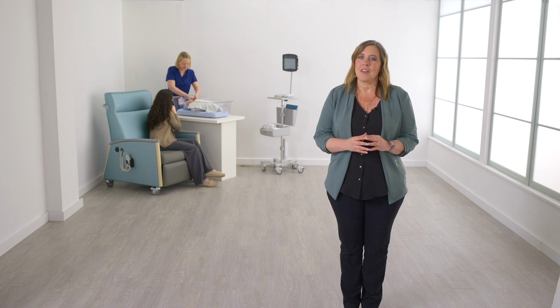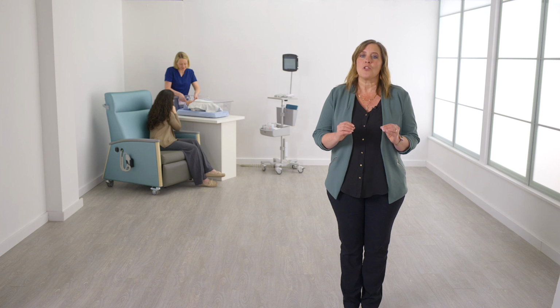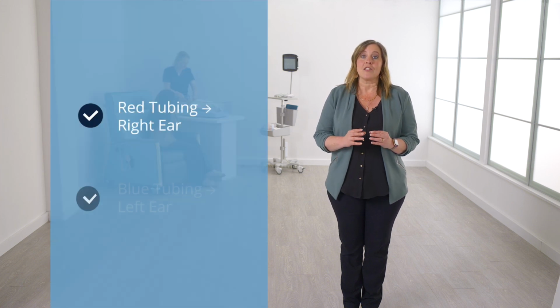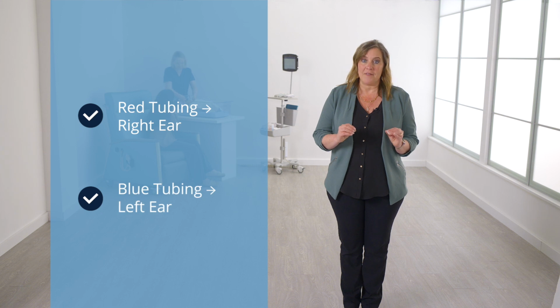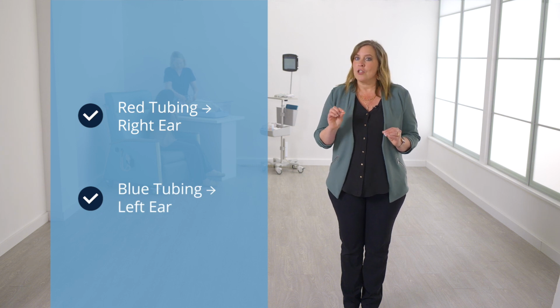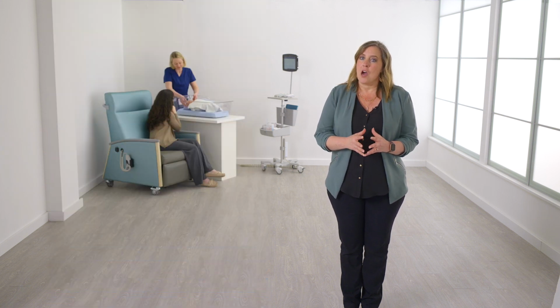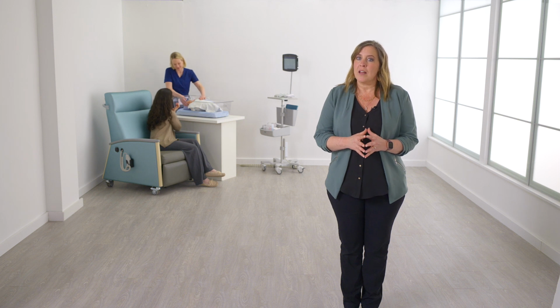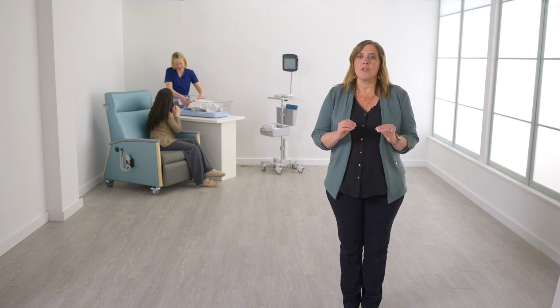Repeat this process for the left ear with the ear tip that is connected to the blue tubing. It is critical that the insert with the red tubing is placed in the right ear and the insert with the blue tubing is placed in the left ear. It's also possible to perform ABR with the OAE probe. There are 2 available probe styles. The procedure for screening is essentially the same for both.